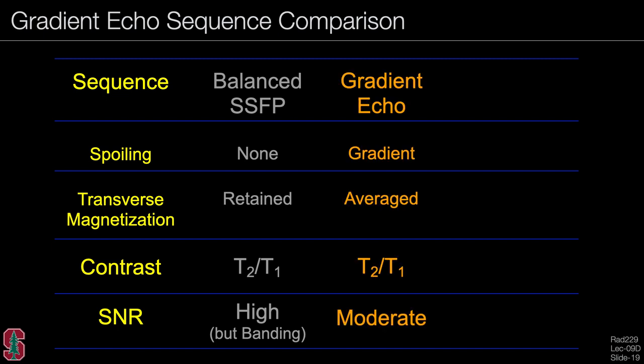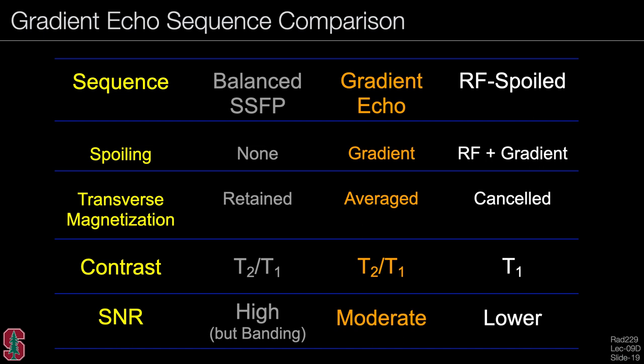Comparing sequences in a chart: balanced SSFP has no spoiling, retaining transverse magnetization, giving T2 over T1 contrast and high signal but with banding artifacts. Gradient echo uses gradient spoiling, which averages transverse magnetization, still giving T2 over T1 contrast but fluids are not as bright, with moderate SNR. RF spoiled imaging uses RF and gradient spoiling, canceling transverse magnetization for a pure T1 contrast, at the price of slightly lower SNR.